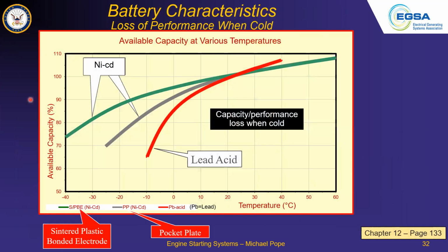Let's talk about the performance of a battery when it's cold. The red line is a lead acid battery. We've got percentage on the vertical scale and temperature on the horizontal, with a Fahrenheit scale for those not bilingual. We get 100% performance at about 70 degrees or so - that's the best point.